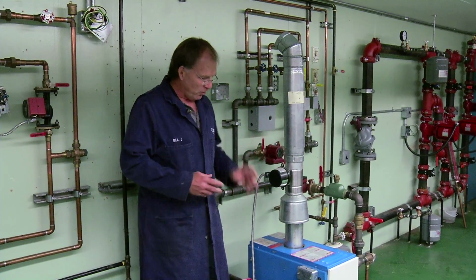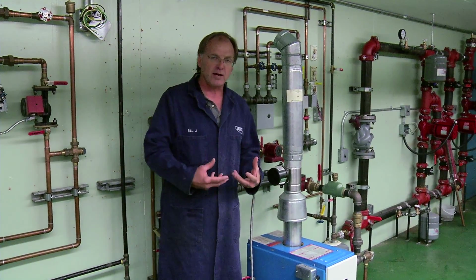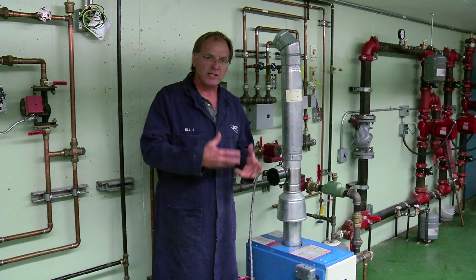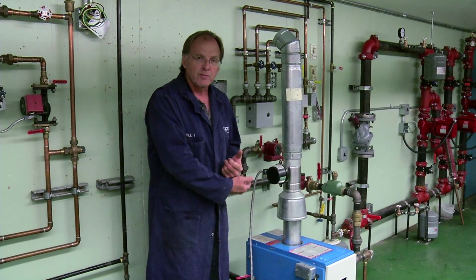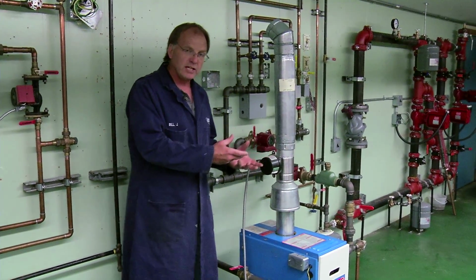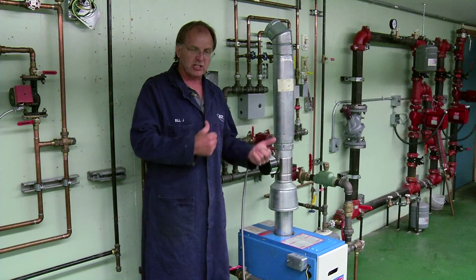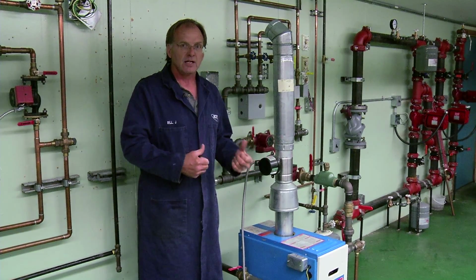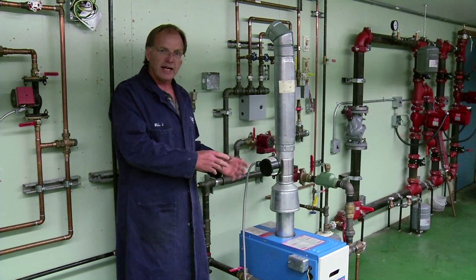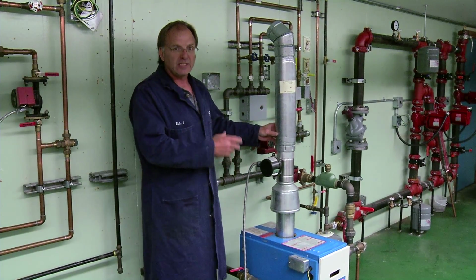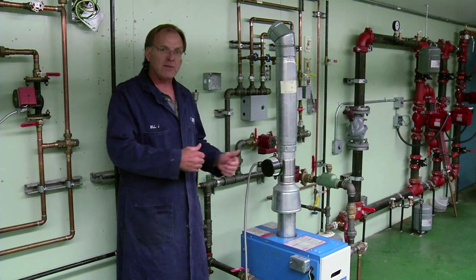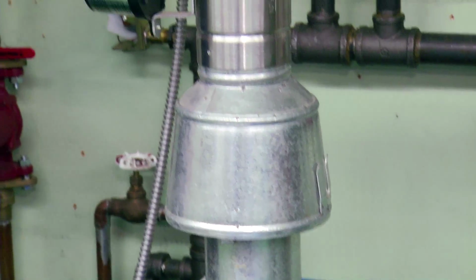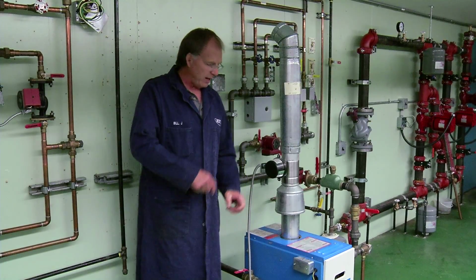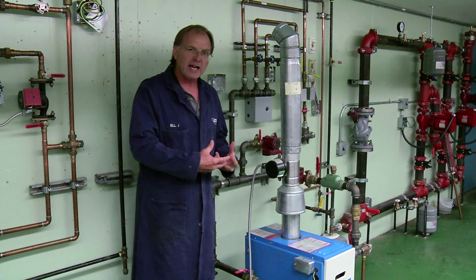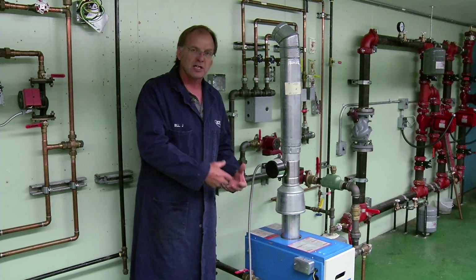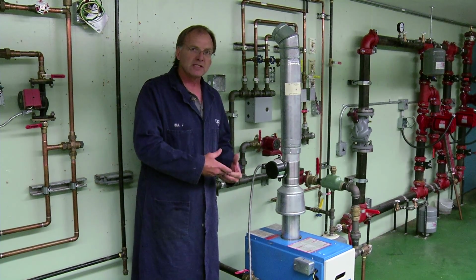vent. Now what happens is when the boiler fires up, the gases ignite, they start heating up air. The air travels from underneath the boiler, goes up through the heat exchanger. The heat is lost to the medium. Some of that heat has to be retained and heat up the stack. That is so that we have enough convection currents to keep that air moving and out of the building before it condenses. Unfortunately, what happens is that stack action can ill affect the burning process and cause it to burn with an unstable flame.